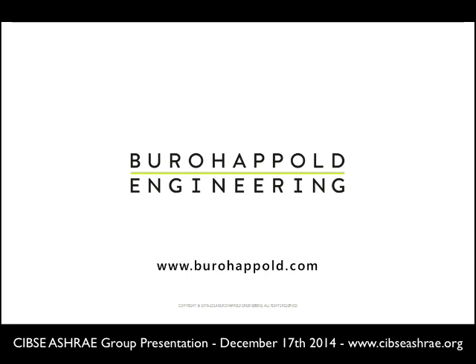I've got a question from Michael, who asks about applying standards for designs - are there opportunities for designers to use a wider band, and allowances for phased commissioning, to avoid the inefficient and expensive use of permanent and temporary plant during construction? There's a requirement to properly service buildings throughout construction, so is it possible to allow conditions to vary more widely than normal to avoid using temporary plant?